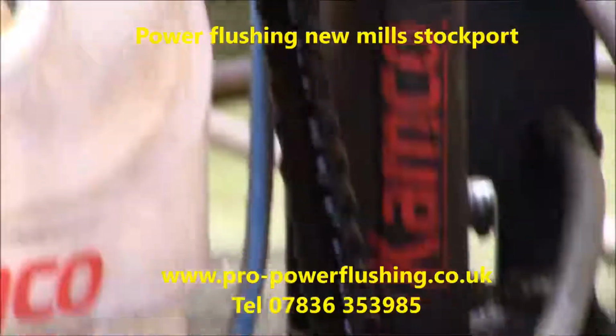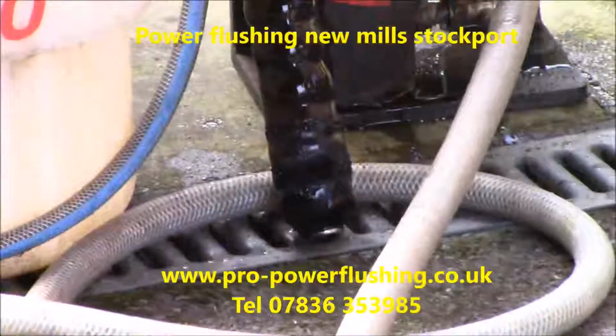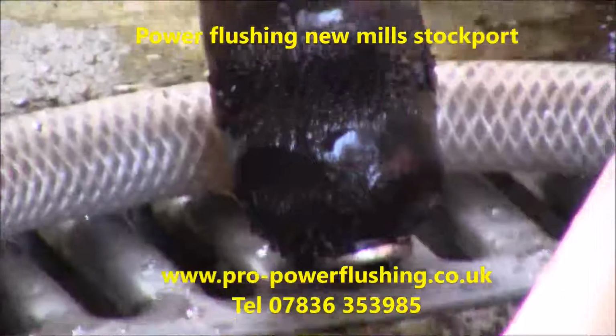Can you see that? That's a magnet that's been in this system before it gets back to the power flush machine. Now we're going to zoom in on that. Now look at this. I'll try and keep this camera steady. Rust and corrosion and metal that's in this central heating system. There's some fairly big pieces on there as well. And this is what power flushing is all about. It's about getting all that rust, corrosion and metal out of the central heating system.